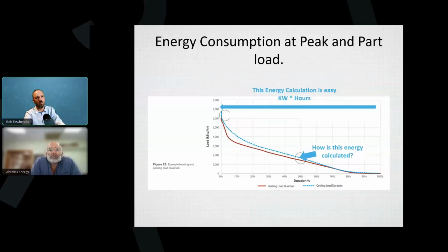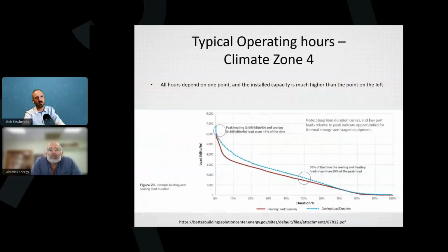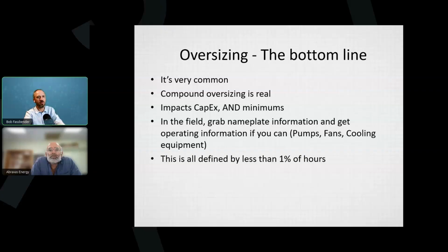The main thing you want to not do for oversizing is this: whatever calculation you're adding, if it's in a spreadsheet and you have the lights and the people in there, when you're adding up the total size of a system, it should not include every single light bulb on at the same time, unless that's going to be on at the same time. You want to define the maximum amount of people in the building at once, how that's going to look, and whether it is going to adjust for their ventilation. And then, of course, how much do you want to oversize? Because you're going to want some oversizing in case the building changes in the future. But in terms of modeling, it's really adding some diversity, and that will size it.